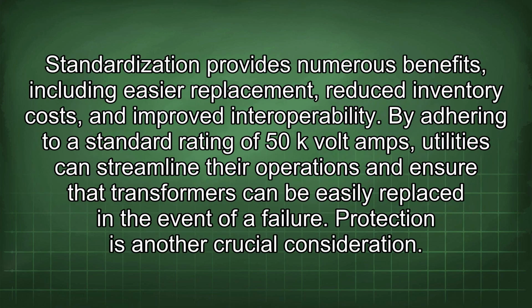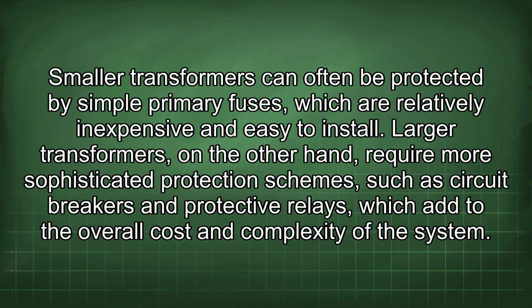Standardization provides numerous benefits, including easier replacement, reduced inventory costs, and improved interoperability. By adhering to a standard rating of 50 kVA, utilities can streamline their operations and ensure that transformers can be easily replaced in the event of a failure. Protection is another crucial consideration. Smaller transformers can often be protected by simple primary fuses, which are relatively inexpensive and easy to install. Larger transformers, on the other hand, require more sophisticated protection schemes such as circuit breakers and protective relays, which add to the overall cost and complexity of the system.